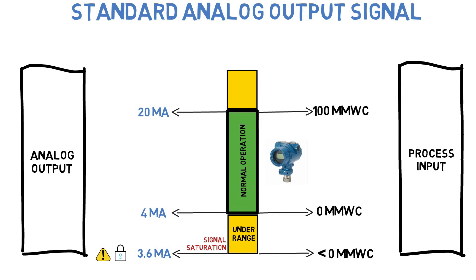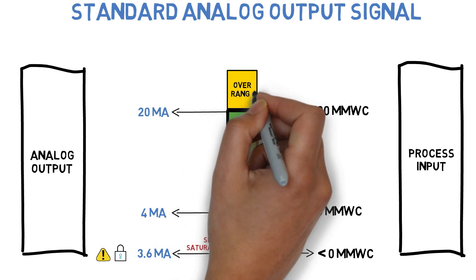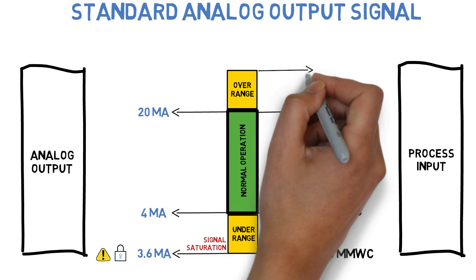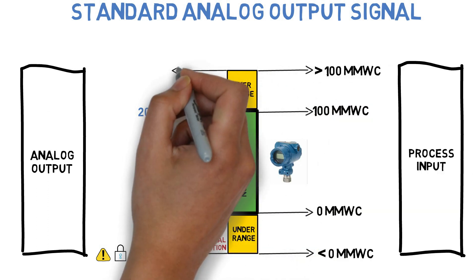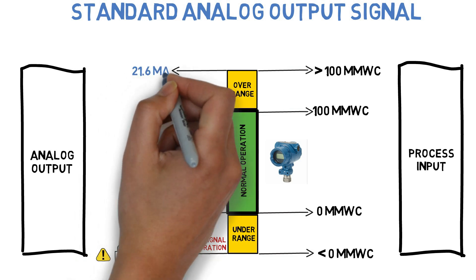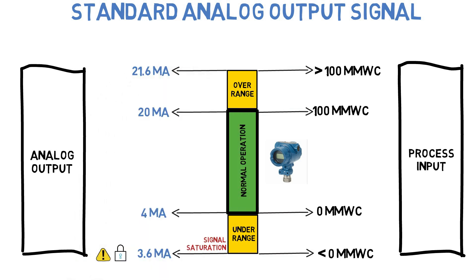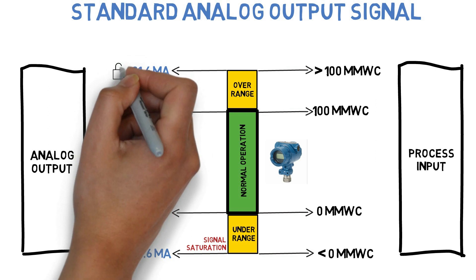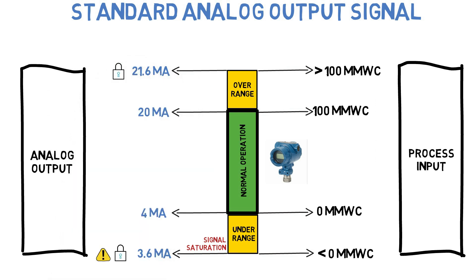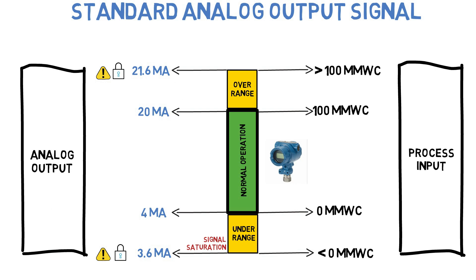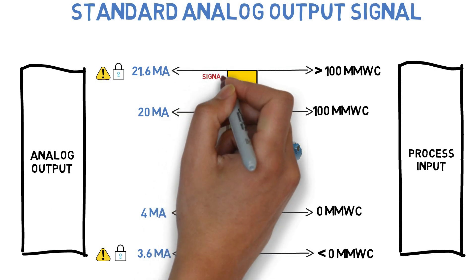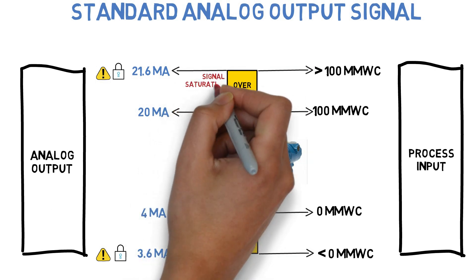If the process input value increases above the upper range value of the transmitter, the analog output signal also increases between 20 to 21.6 mA. If the process input exceeds the upper range value, the analog output holds at 21.6 mA with a warning to the control unit. This over-range signal is also referred to as Signal Saturation.